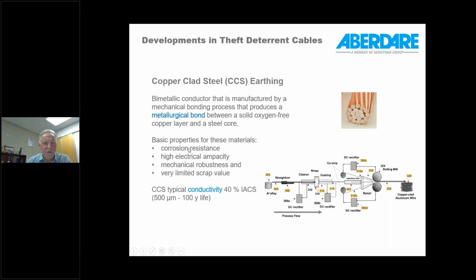So the basic properties of these materials are high corrosion resistance, reasonably high electrical ampacity, mechanical robustness, and very limited scrap value. If scrap of copper-clad steel or copper-clad aluminium is melted together with copper scrap, it can really cause havoc for the scrap dealer or recycler through the contamination that this would create. Generally the most common conductivity for copper-clad steel is 40% IACS, which is 40% of the copper conductivity standard, and a 500 micrometer thick layer of copper relates to a 100-year life for this metal. So it's good to be installed underground, buried directly as well.